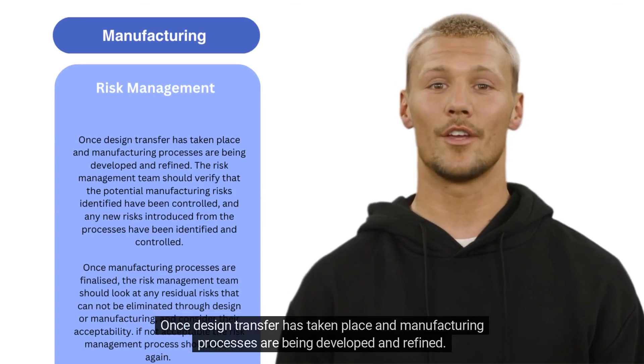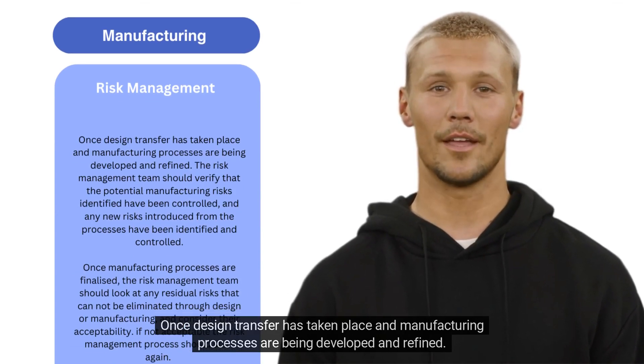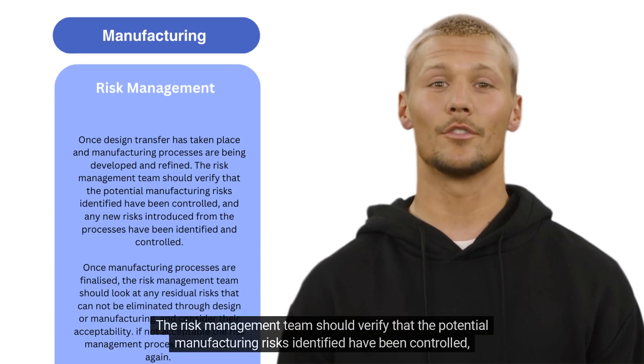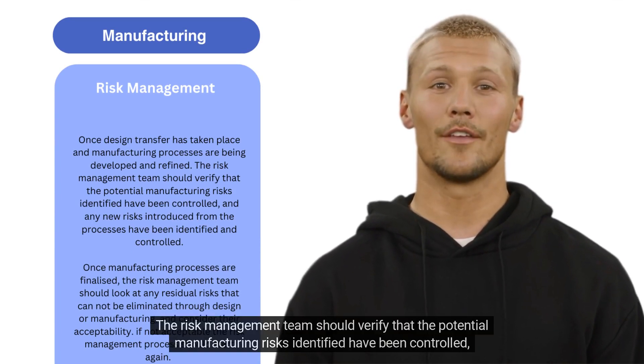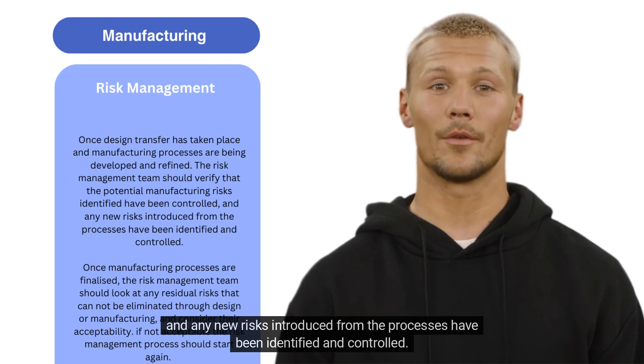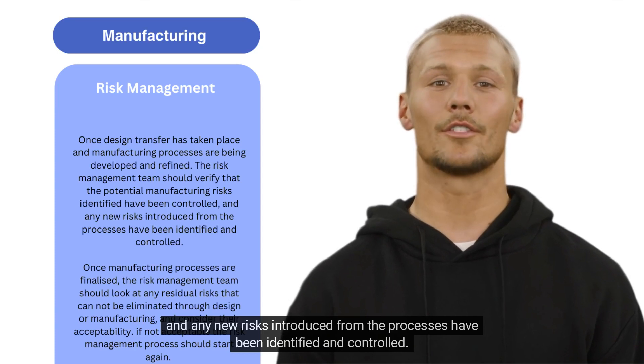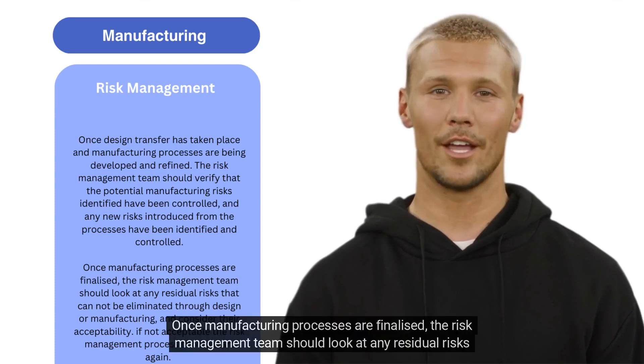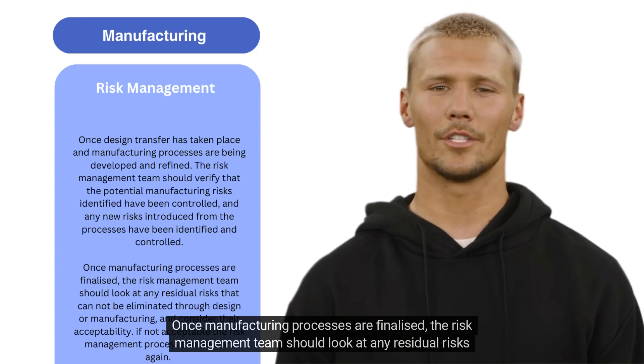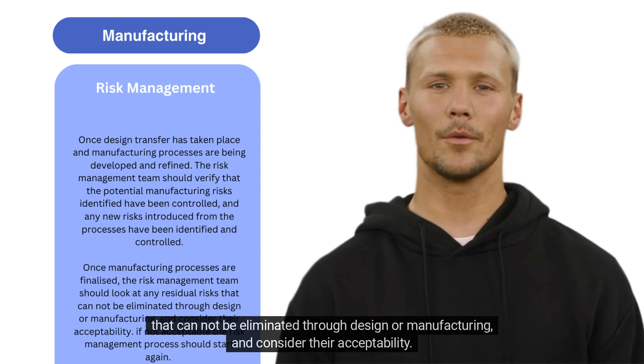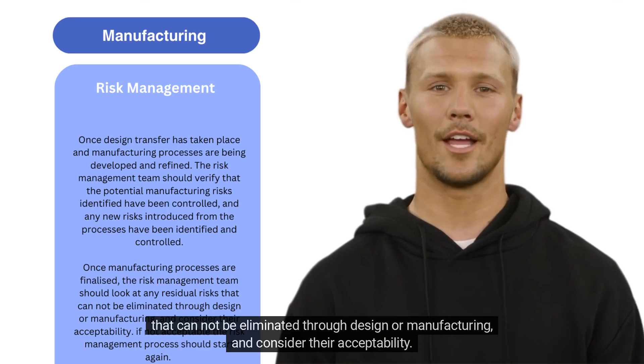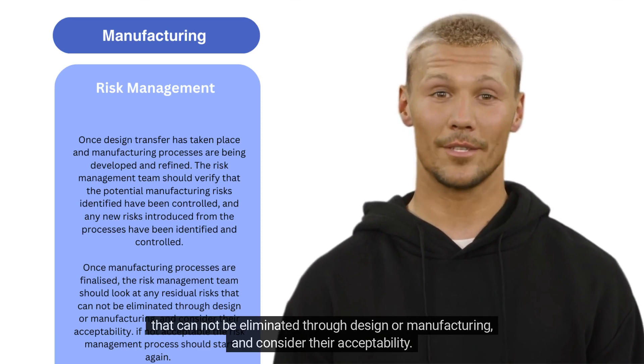Once design transfer has taken place and manufacturing processes are being developed and refined, the risk management team should verify that the potential manufacturing risks identified have been controlled and any new risks introduced from the processes have been identified and controlled. Once manufacturing processes are finalized, the risk management team should look at any residual risks that cannot be eliminated through design or manufacturing and consider their acceptability.